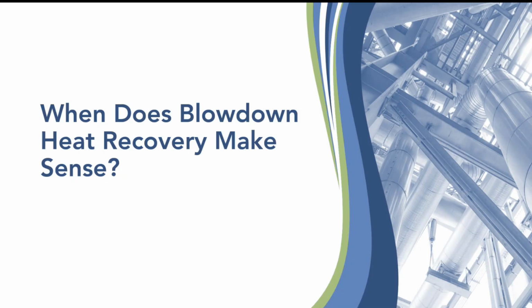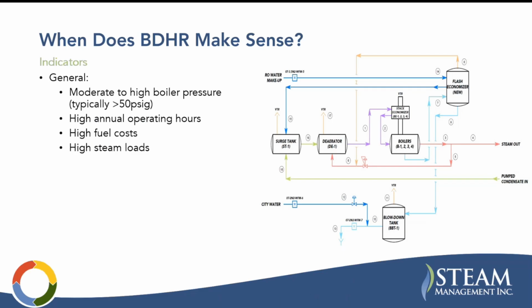When does blowdown heat recovery make the most sense? This is like, if I go into a facility, what am I looking for if I'm going to start thinking about this? Generally speaking, it's going to work better with moderate to high boiler pressure. I would say greater than 50 pounds. I do want to stress that these are general clues, not hard and fast rules. But the higher the pressure, the more energy that blowdown has. Obviously, higher annual operating hours, higher fuel cost, and higher steam loads, kind of like any other energy conservation measure, right? The more it's used, the more energy is available to save. And that's true here too.